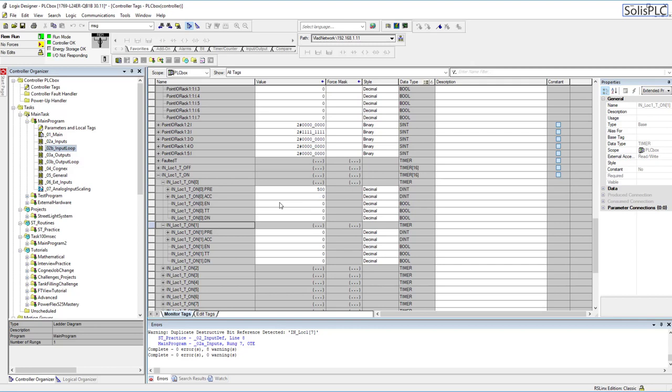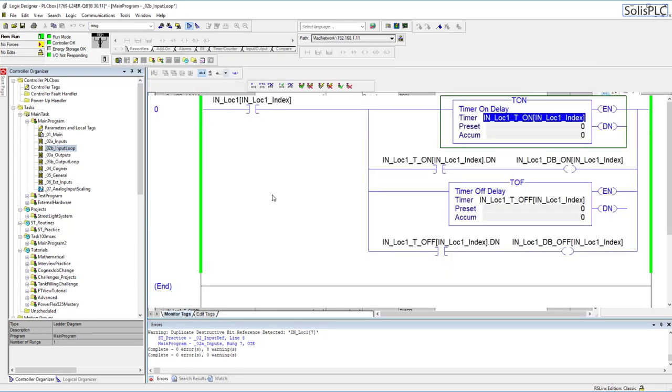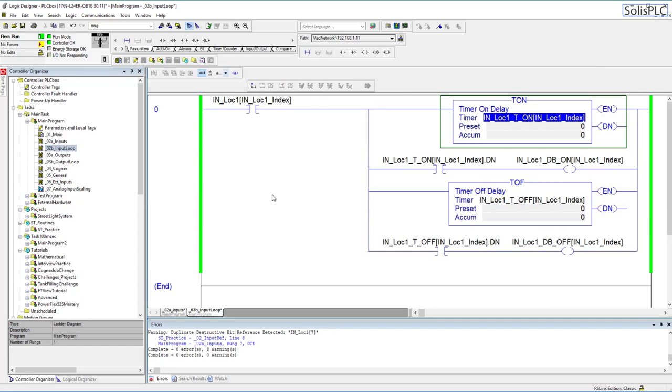The preset is going to be 500 which effectively means that once something goes in front of the sensor the accumulated value doesn't trip the sensor immediately but instead it goes to a different boolean which could be used to debounce this photo eye. When a box comes in front of this photo eye it takes 500 milliseconds to actually confirm that the box is there and this prevents false triggers where for example the box vibrates on the conveyor which may trigger it unnecessarily.